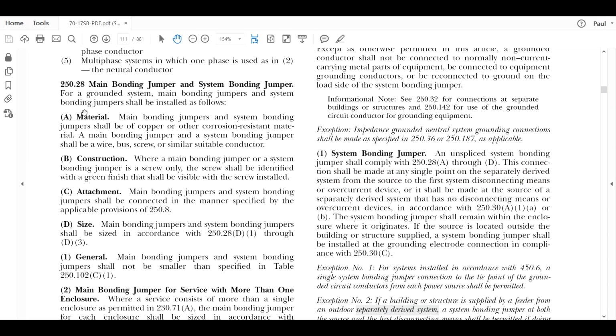That's the rule. Now, sizing is over here, 250.28, and the material. For our system bonding jumper, in our case, it can be copper or other corrosion resistant material. That's copper, or it could even be aluminum, because aluminum is corrosion resistant, despite what people might think. The system bonding jumper can be wire, bus, screw, or similar suitable conductor. Now, similar suitable might be something that's provided by the manufacturer. If you want to do your system bonding jumper inside of the panel where the disconnect would be, then you might use the screw. Sometimes we call that the main bonding jumper, but it could be the system bonding jumper if you're doing all this inside of the first disconnecting location. That's possible. Just remember that your grounding electrode conductors also have to go to the same place wherever you do this system bonding jumper location. Just keep that in mind.